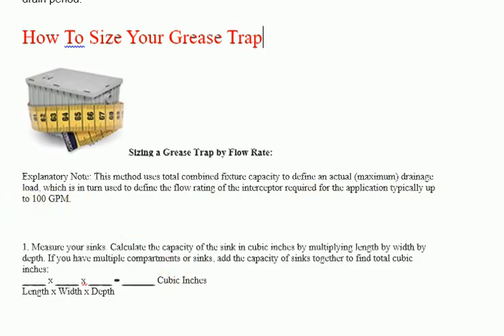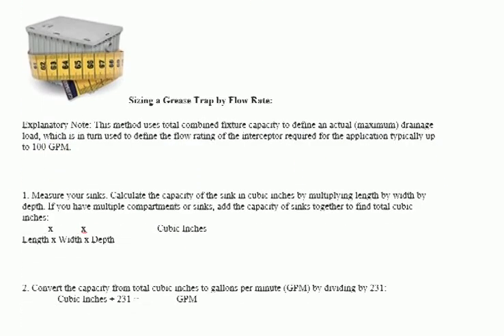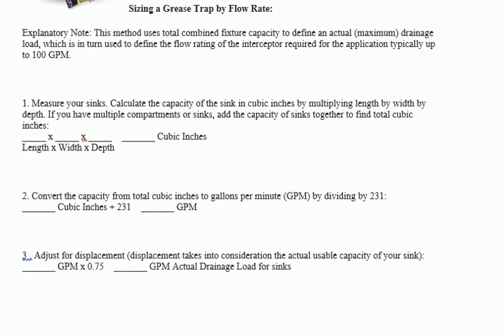Step 1 — Measure your sinks: Calculate the capacity of the sink in cubic inches by multiplying length by width by depth. If you have multiple compartments or sinks, add the capacities together to find total cubic inches.